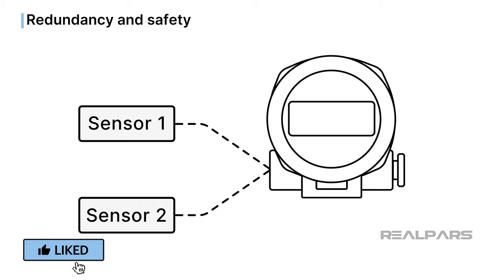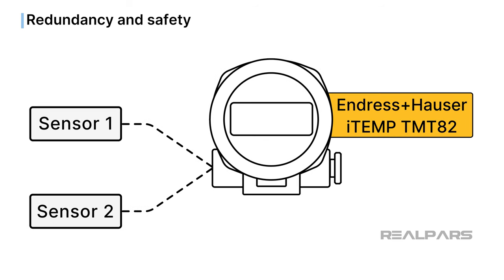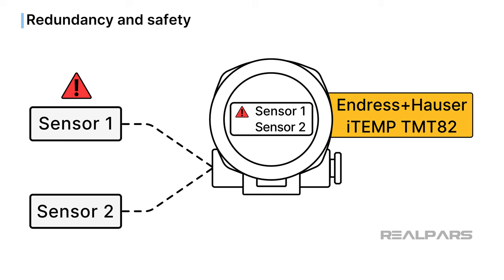Before we move on to NAMUR NE107, let's discuss the dual-sensor redundancy and fail-safe features of some smart transmitters, such as the Endress+Hauser iTEMP TMT82. Dual-sensor redundancy involves using two separate temperature sensors. If one sensor fails or malfunctions, the transmitter can switch to the other sensor, ensuring a fail-safe environment and maintaining continuous and accurate temperature monitoring. If the transmitter is capable, both sensor outputs are compared in real-time to detect abnormalities or faults such as sensor drift, thus signaling the need for maintenance or replacement.